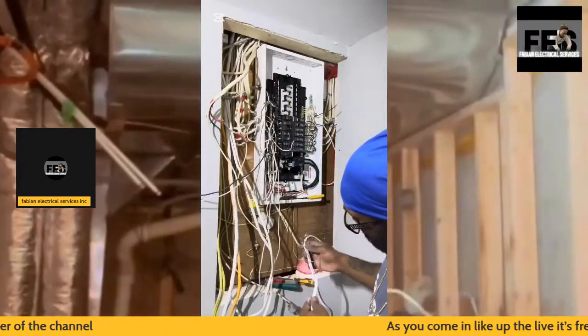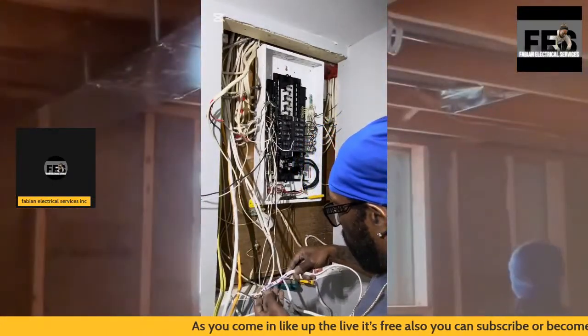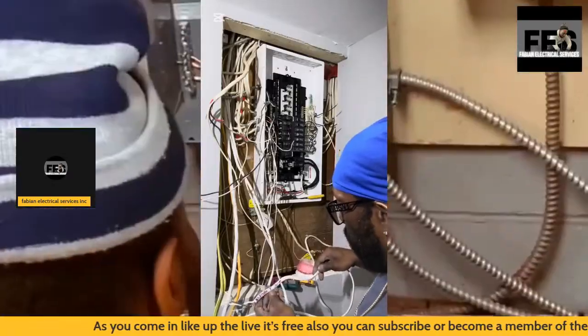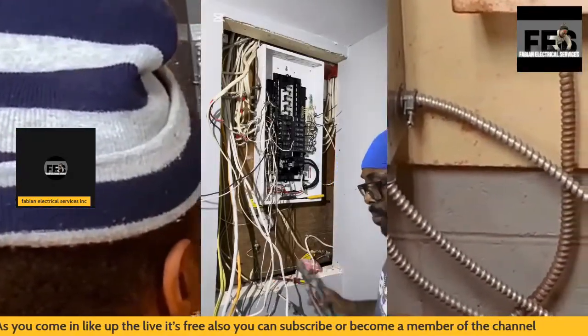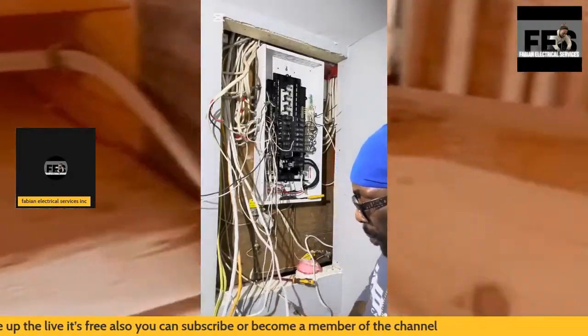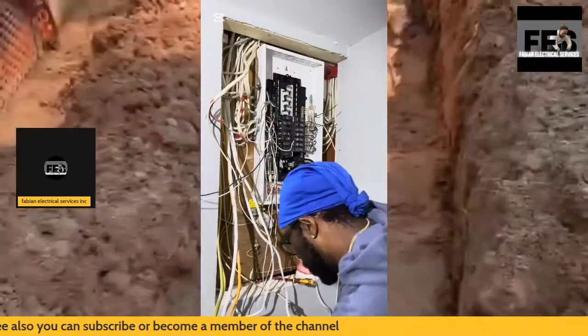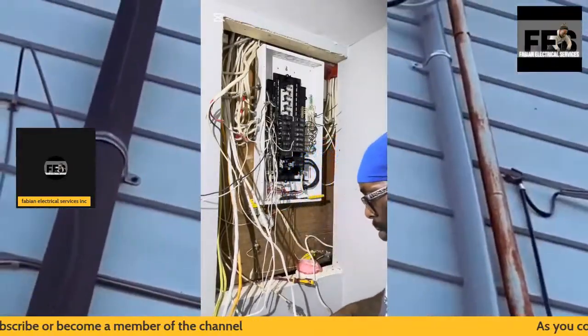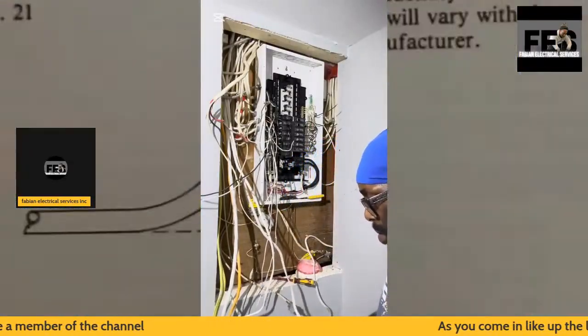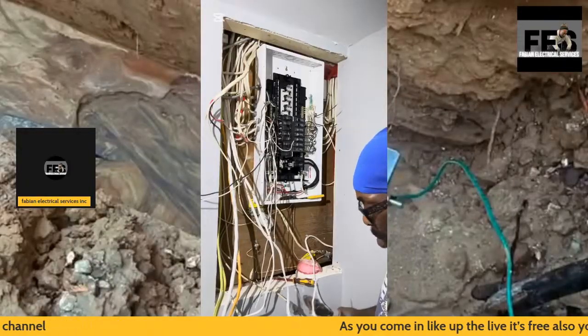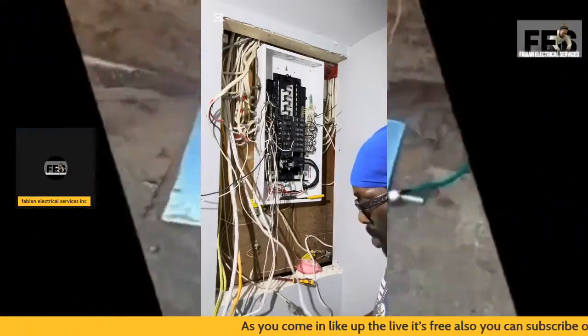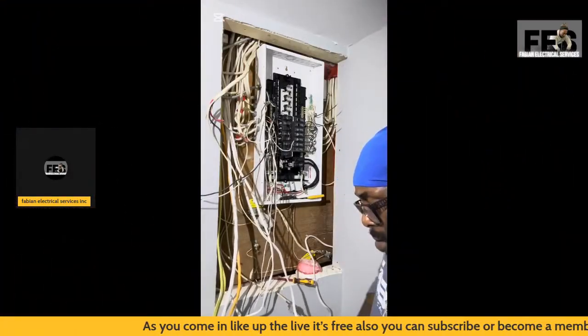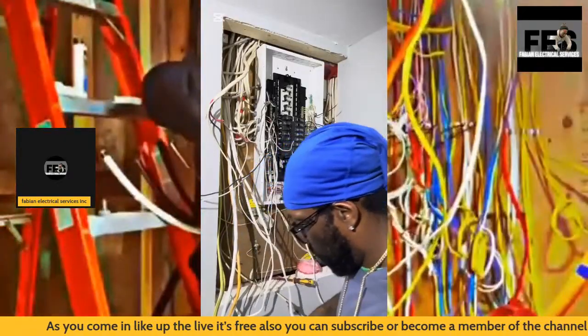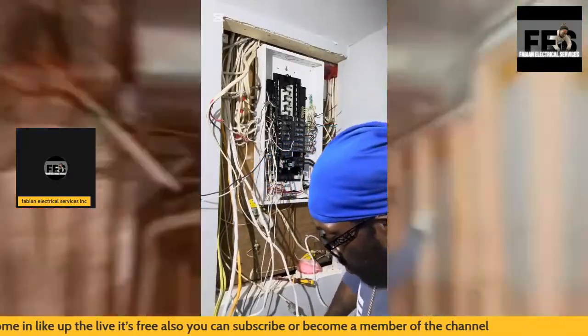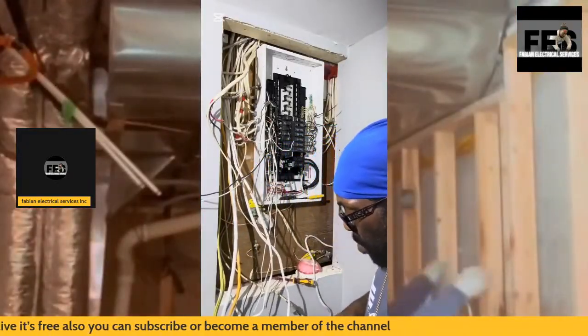What you can see here is me labeling my wires. These wires were labeled before the older panel was pulled out. It's very important to remember to label your wires before you remove your older panel, so that you don't have to go back at the end of the job troubleshooting your circuits. It takes a lot of wasted time that doesn't need to happen.